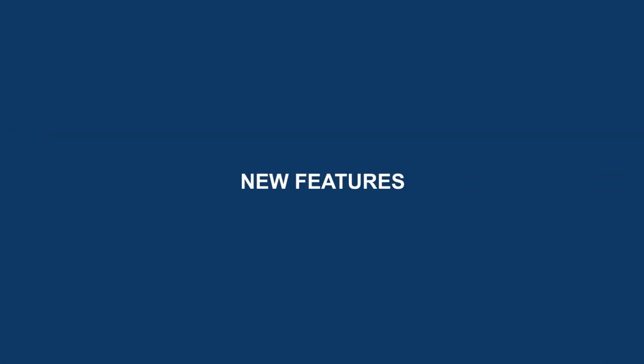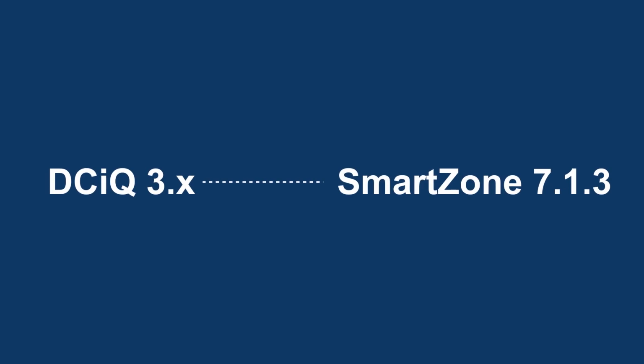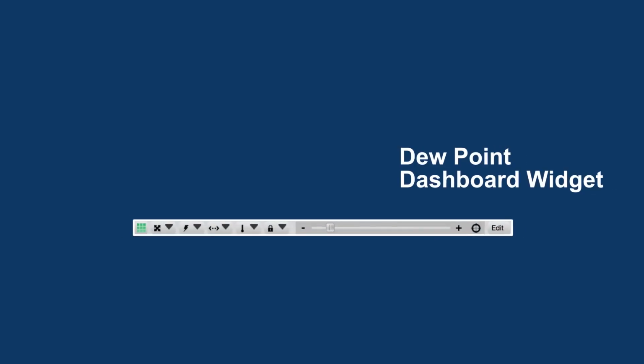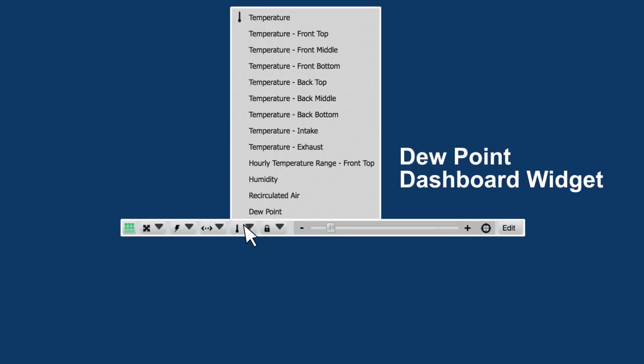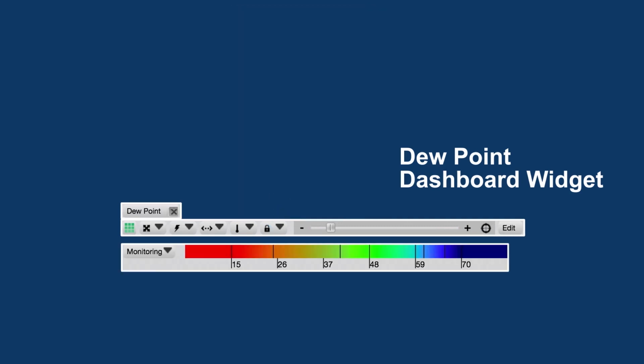Next, let's take a look at a few key new features in this release. The first feature we want to discuss is the migration of DCIQ data to the SmartZone database. If you are currently a DCIQ 3 customer and are looking to upgrade to SmartZone, it is now possible to have all of your existing DCIQ data migrated into SmartZone. During the migration, both the DCIQ long-term and short-term databases are combined into a single database, with that data accessible in SmartZone. A new dew point option has been added to the environmental menu, and dew point readings can be tracked and monitored in the same way that temperature and humidity readings are today.